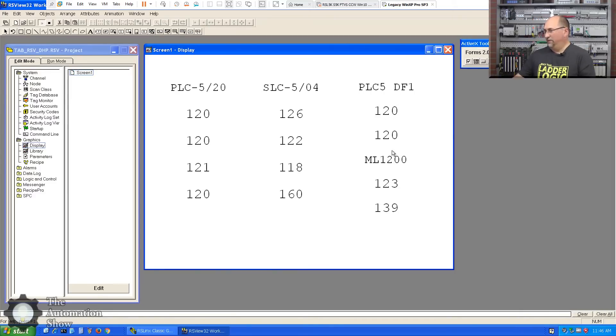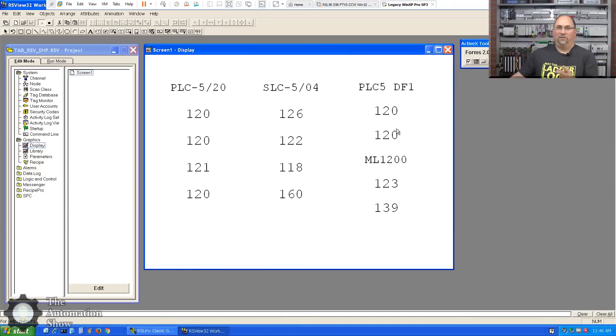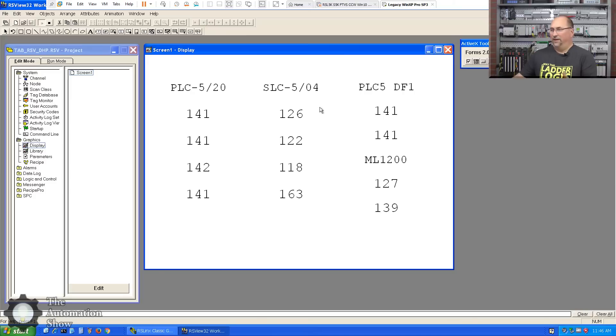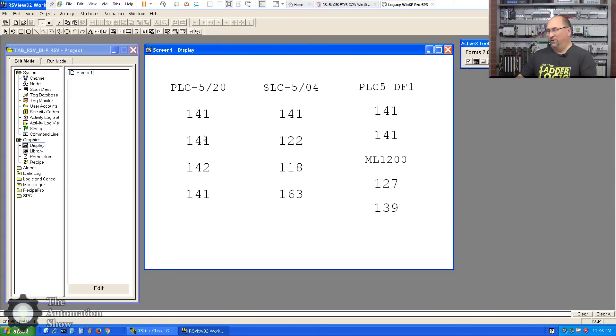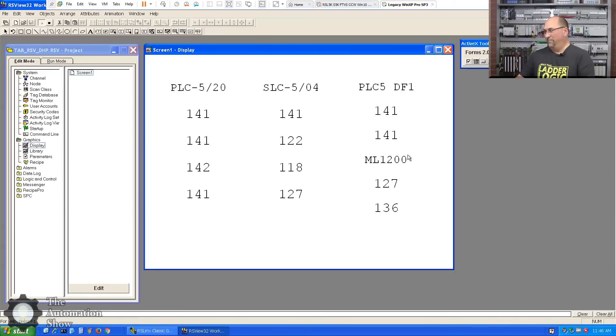All right, let's see if it works. Yes, it's working! Because the PLC-5, you know, it's those timers I have in there. They're just - the PLC-5 is so fast compared to like the Micros and the SLCs that there's not a lot of variability in the timer, so they all kind of end up being the same number. Whereas in the other ones there's a lot of variability in them. But in any case, there we go. So we've successfully used the direct drivers, the channels in RSView32 to talk to some legacy networks. We did DF1, we did DH485. And you know, I didn't have any success with that DF1 direct driver, so that was a time sink. But everything else seems to work great. And with that, that's the end of this episode.